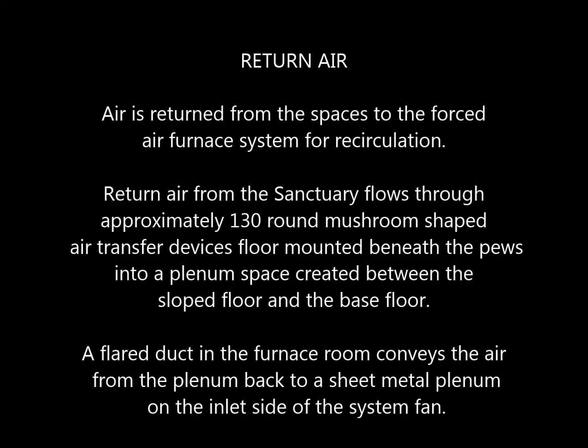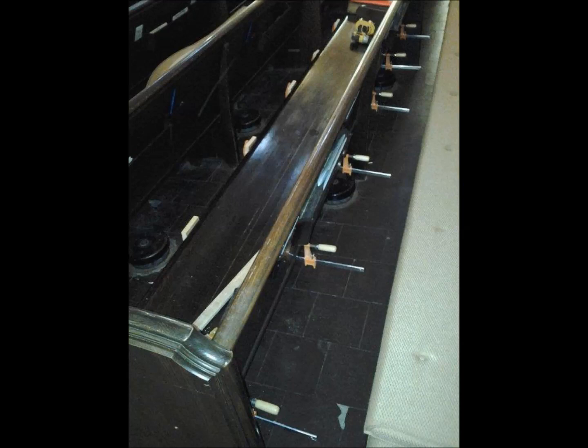Return air. Air is returned from the spaces to the forced air furnace system for recirculation. Return air from the sanctuary flows through approximately 130 round mushroom-shaped air transfer devices, floor-mounted beneath the pews, into a plenum space created between the sloped floor and the base floor. A flared duct in the furnace room conveys the air from the plenum back to the sheet metal plenum on the inlet side of the system fan.